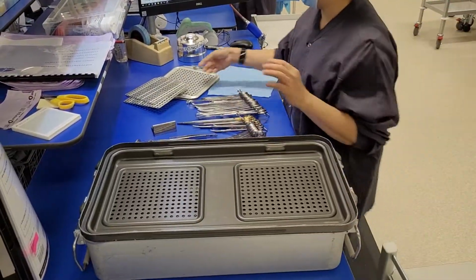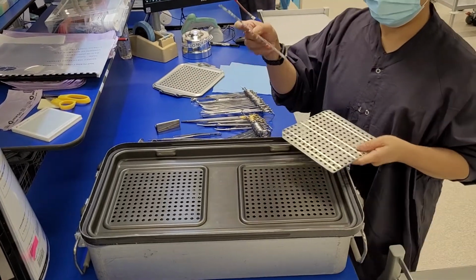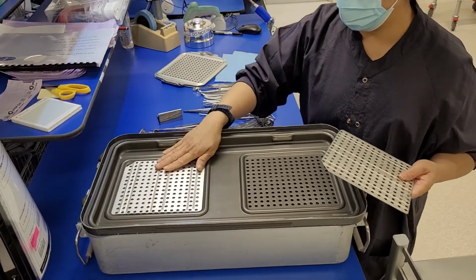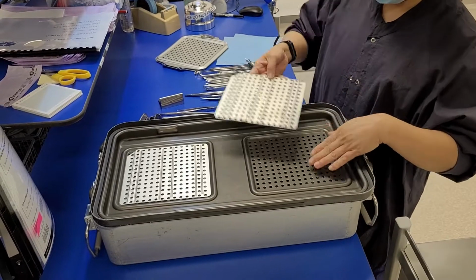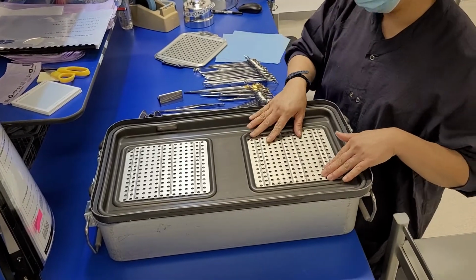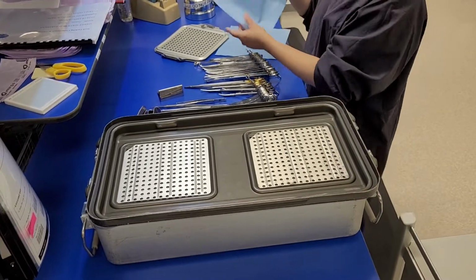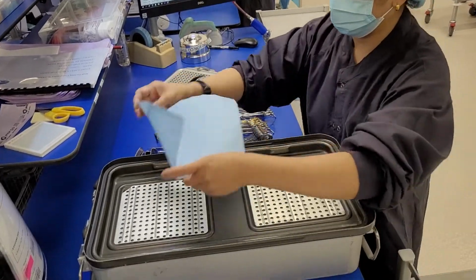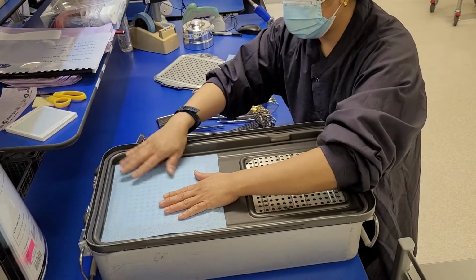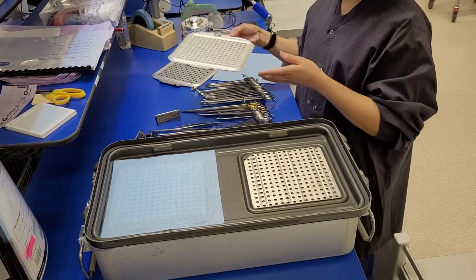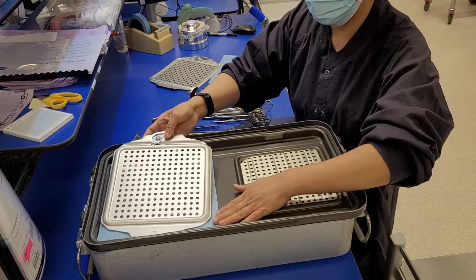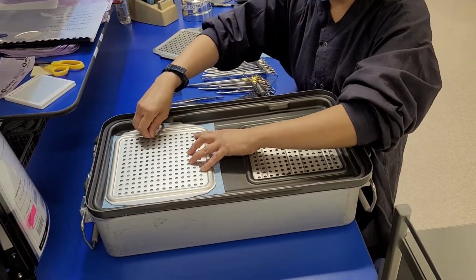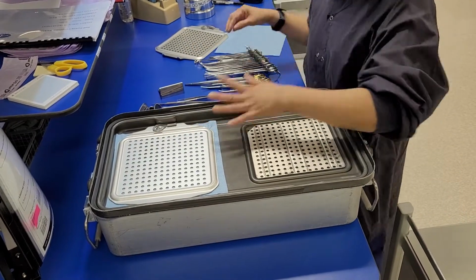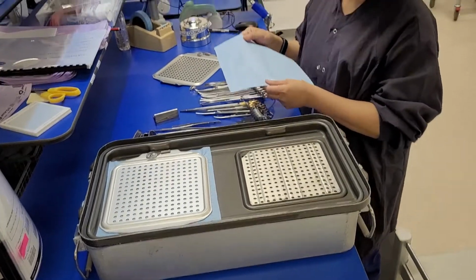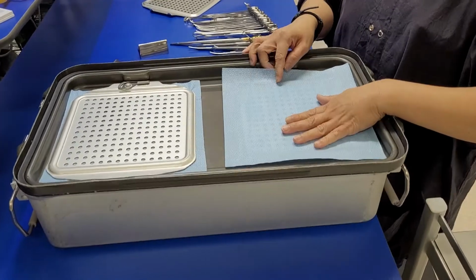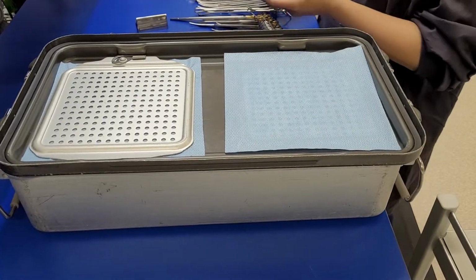This is the filter material placement for the Genesis container. Place one filter over the entire filter lid surrounding its sterilant access hole area in a container lid or bottom. The filter material should overlap the filter ridge on all four sides and will be secured between the filter retention plate and the lid or bottom when assembled. Make sure the filter does not overlap itself or become wrinkled or creased.